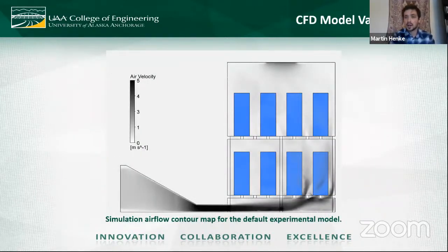You can see here is my actual simulation. Before I said that batteries, I believe, towards the back of the case tended to be cooler, and we can actually see why using the simulation. You'll notice that batteries towards the back receive significantly more airflow, and I'm sorry if I didn't explain, but air velocity is represented by the black mist that you see moving through the model.